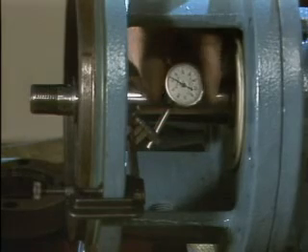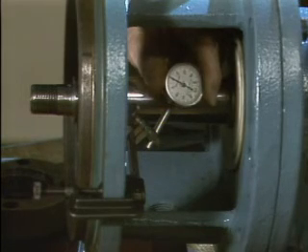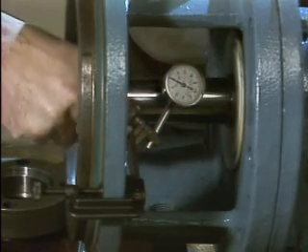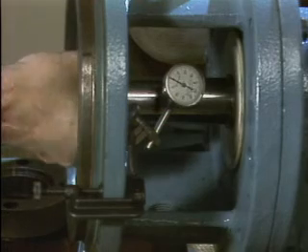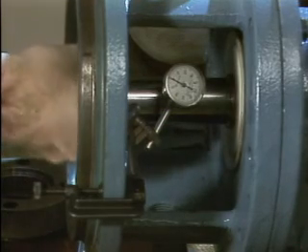There are other important checks that should be made before a mechanical seal is installed. Some of these checks involve the use of dial indicators. One important check is testing for shaft runout. A shaft that's bent or out of round can damage pump components and prevent a mechanical seal from operating properly. Before the measurement is taken, the dial indicator is zeroed. Then the shaft is rotated. The dial indicator should measure any shaft runout that's present.